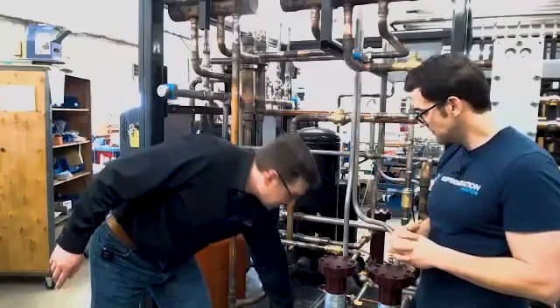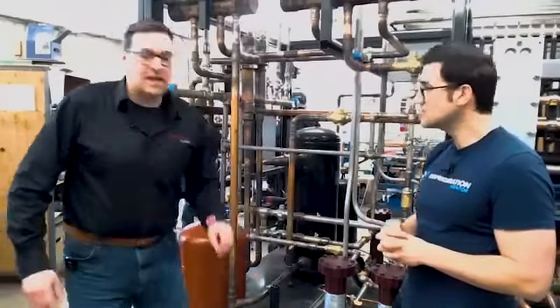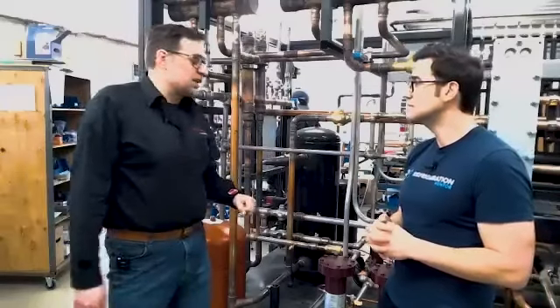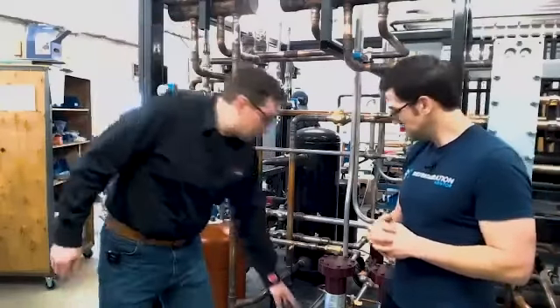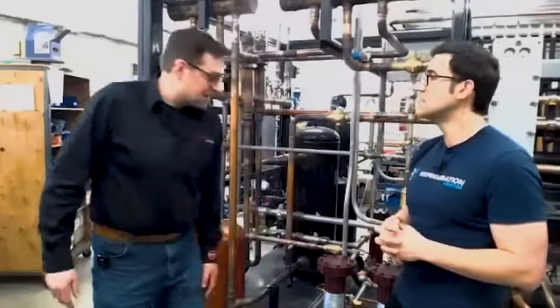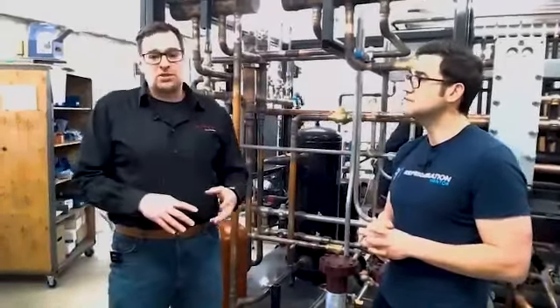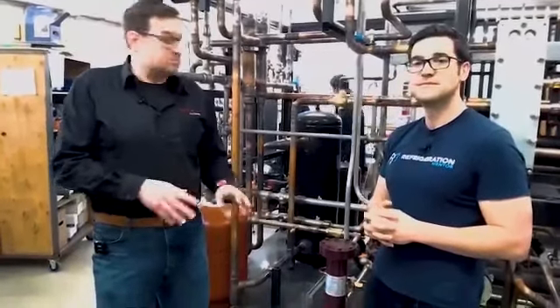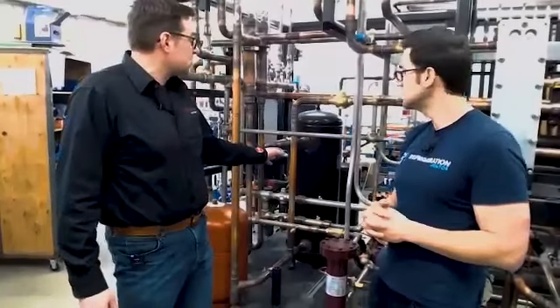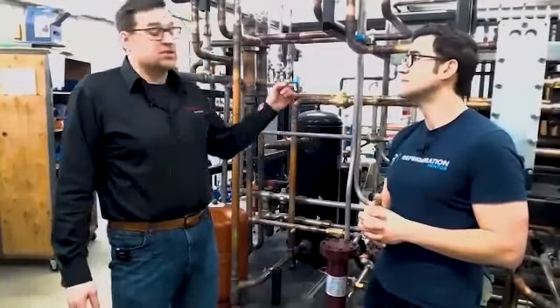I can speak for Arneg. I know there are a few different philosophies out there, but we use two principal designs: on-demand or continuous flow. On-demand is when the oil reservoir is full, a photo eye gives the demand signal, we open up a valve, and feed oil in through the lines. Continuous is a constant flow, with no photo eye on the temp or any type of oil separator, so it's flowing continuously. For smaller machines, we typically use a high pressure, continuous oil flow design. We select compressors that can adequately handle the high pressure oil flow, and we do not depressurize the oil reservoir into the flash tank.